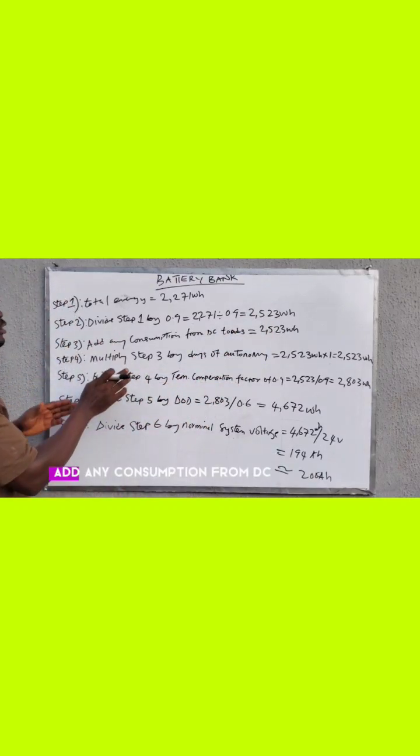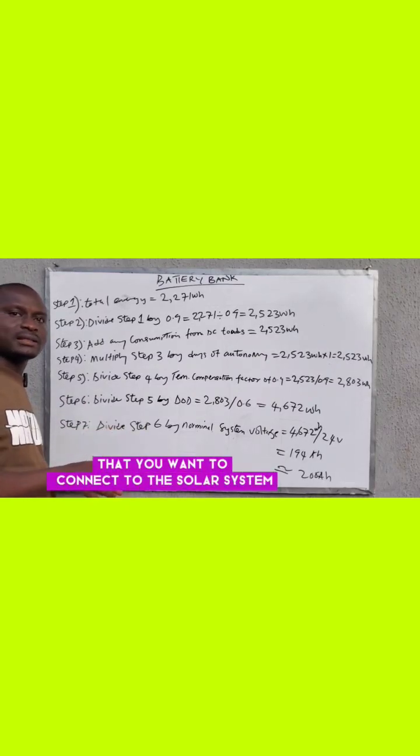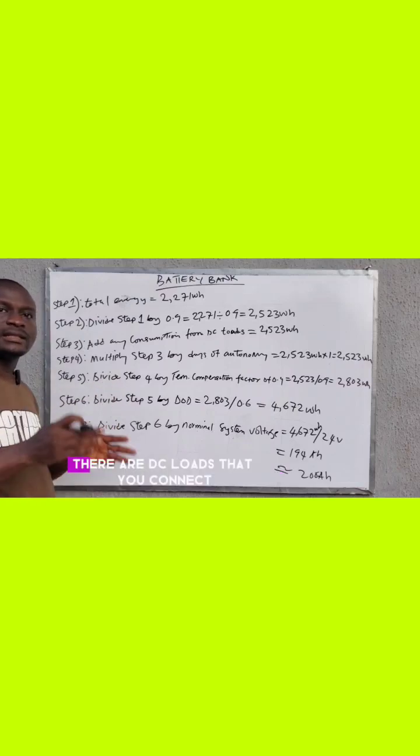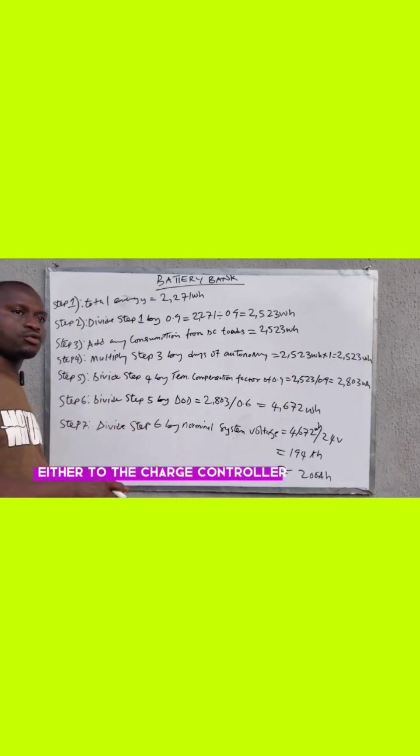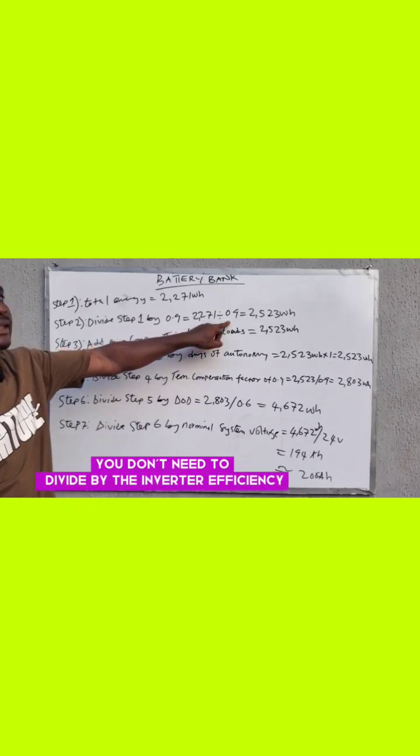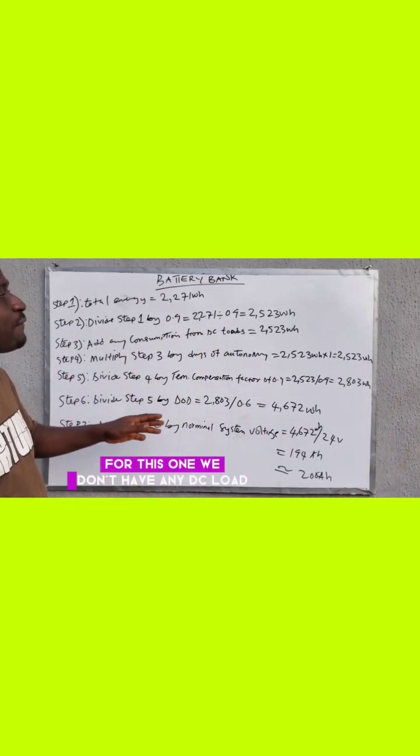Step three: add any consumption from DC loads. Now if you have DC loads that you want to connect to the solar system, you know the DC loads aren't connected directly to your inverter. There are DC loads that you connect either to the charge controller or directly to your battery bank. So you don't need to divide by the inverter efficiency because you're not connecting them to the inverter. For this one, we don't have any DC loads.